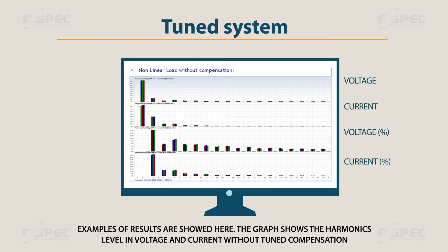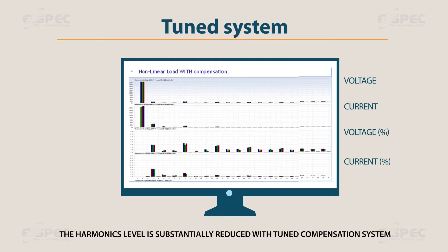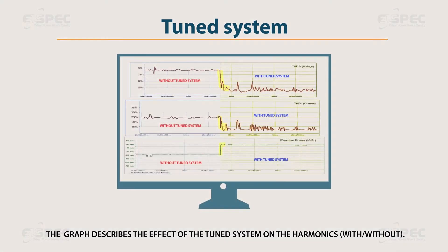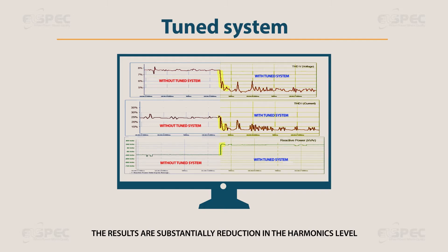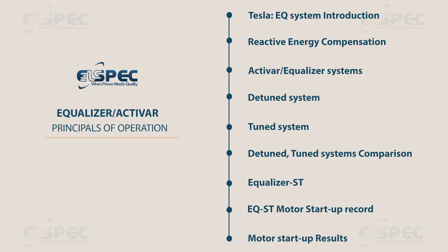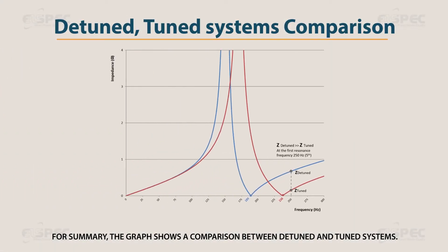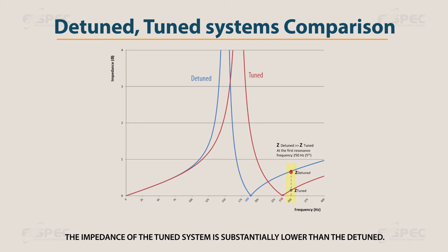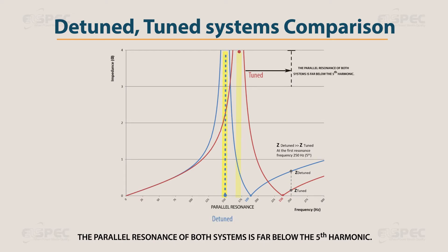Examples of results are shown here. The graph shows the harmonic level in voltage and current without tuned compensation. The harmonic level is substantially reduced with the tuned compensation system. The graph describes the effect of the tuned system on harmonics, with and without — results show substantial reduction in harmonic level. A comparison between detuned and tuned systems shows that the series resonance frequency of the tuned system is at the vicinity of the 5th harmonic at 238 Hz, and 189 Hz for the detuned. The impedance of the tuned system is substantially lower than the detuned, while the parallel resonance of both systems is far below the 5th harmonic.